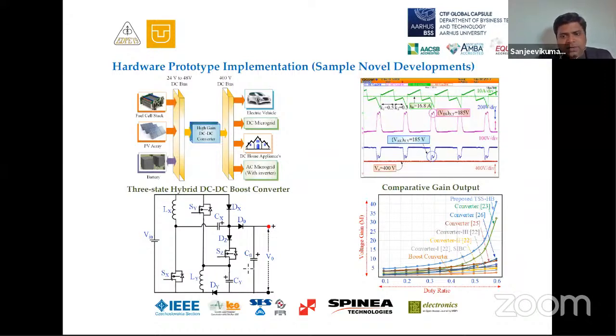Once we design the converter, we look at its close performance. We try to use the power only between 10 to 60%, with the maximum power usage at 60%, but we bring a higher output value. In this case, when the devices are conducting between 10% and 60% utilization of the DC bus, we get a gain around 42 compared to all existing solutions in literature or practice.